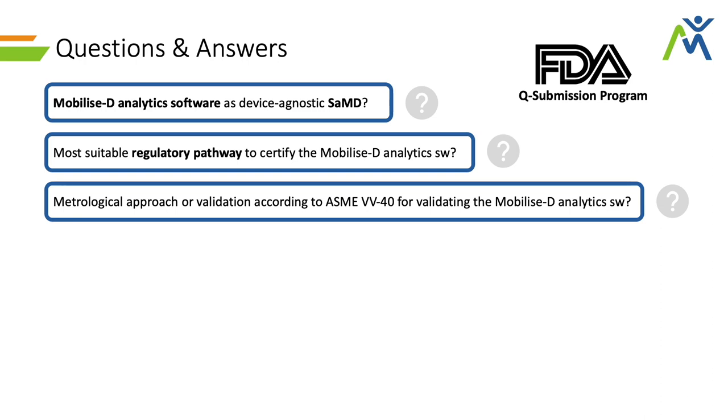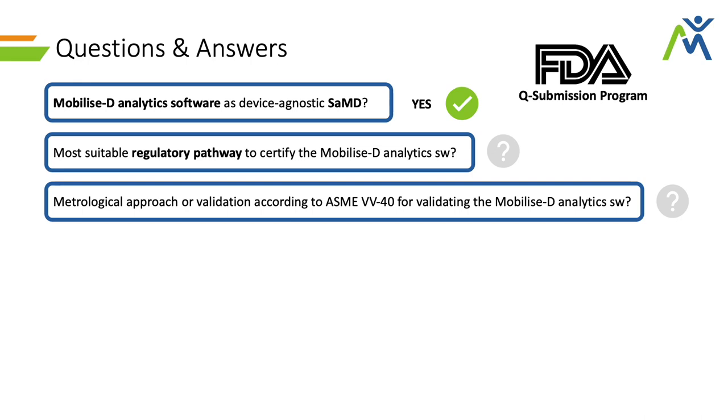We covered some basics: first, we asked whether, given the description of the pipeline, we could consider the Mobilise-D pipeline as a software as a medical device — and the answer was yes. Then we asked whether there was a specific regulatory pathway we should be following. Given that there were no precedents or other devices that were software as medical devices looking at the same context of use — in this case MS — we were told that if we were going to request marketing authorization, we should start with a De Novo application, since we couldn't look for similarity anywhere else.